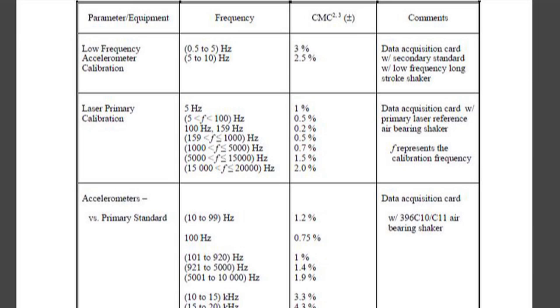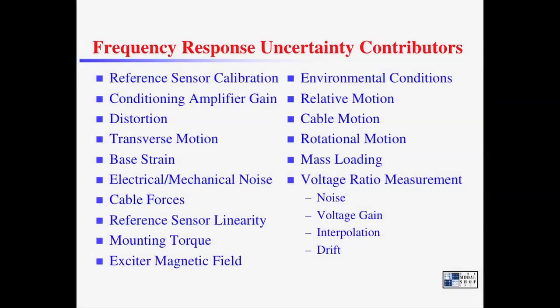The true response of an accelerometer can never be measured with complete accuracy. In other words, there is some level of uncertainty associated with performing a calibration. Part 21 of the ISO 16063 standard lists which factors contribute to uncertainty and should be considered when making an uncertainty statement. Most components are dominant either at high frequency or at low frequency.